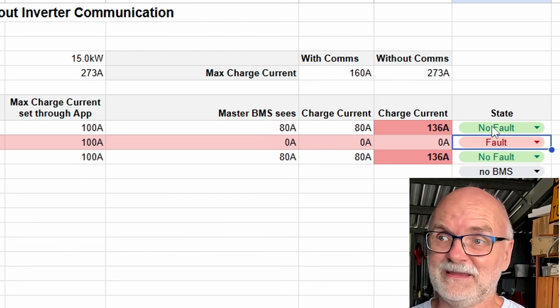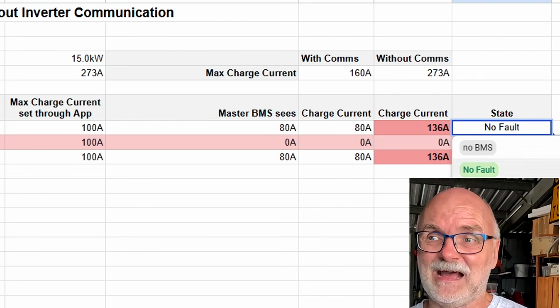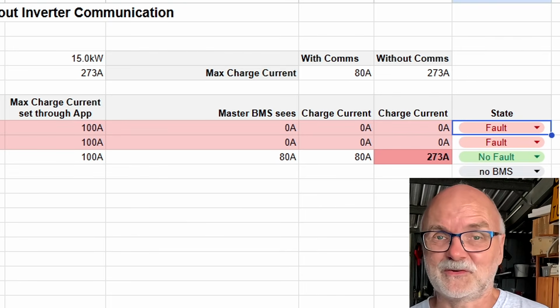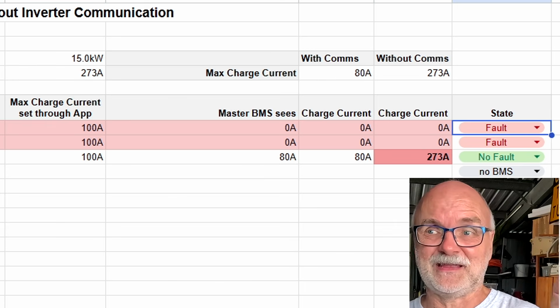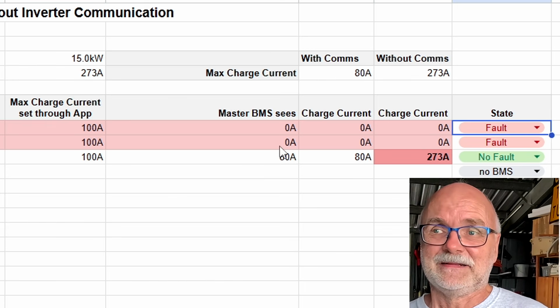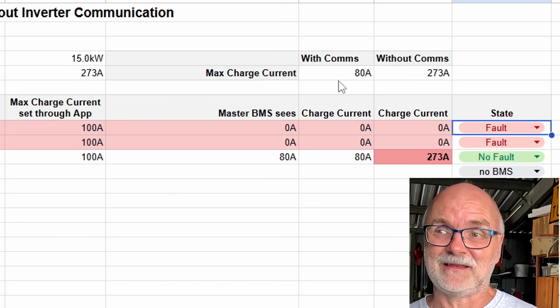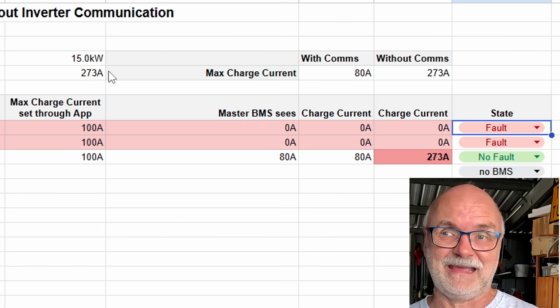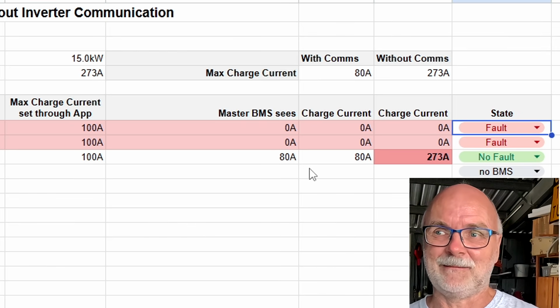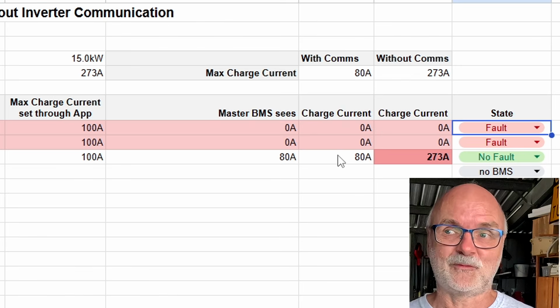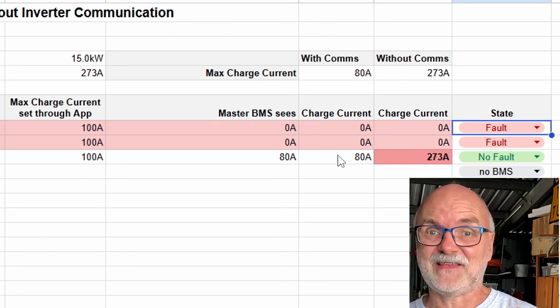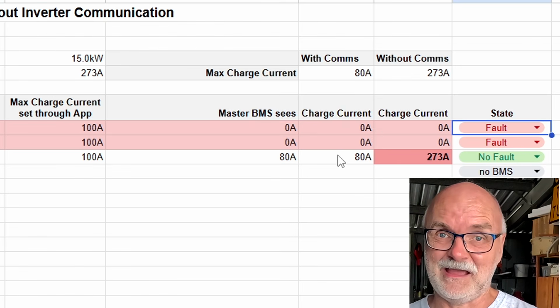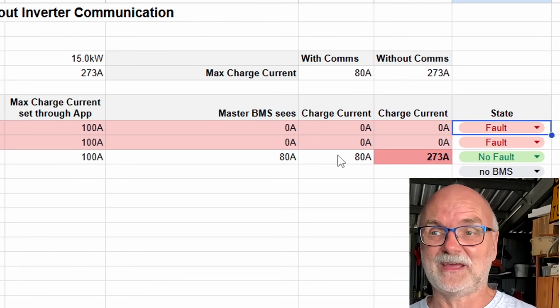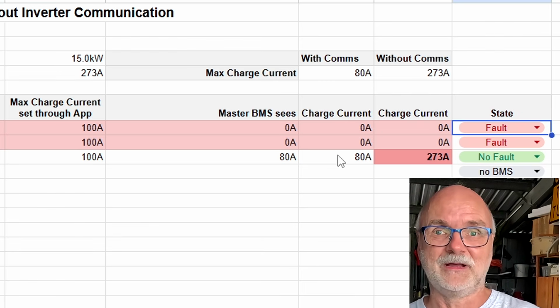If, for whatever reason, another battery goes out with an over temperature protection because I have plugged this stupid temperature sensor into the circuit breaker, Master BMS realizes that and says, hey, I've got only one battery left, charge only with 80 amps. Even if your solar can deliver full power, 270 amps, we are charging your battery with 80 amps. Everything stays safe, everything stays online. And I'm also getting the notification on the mobile phone through the Victron system. You would get a notification on your inverter, something is wrong.